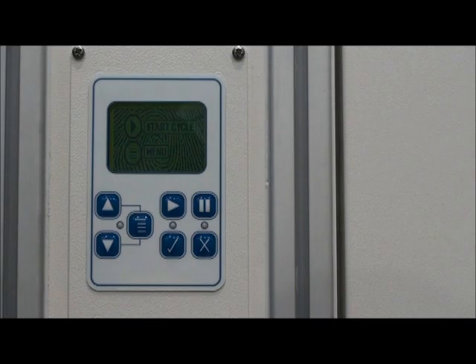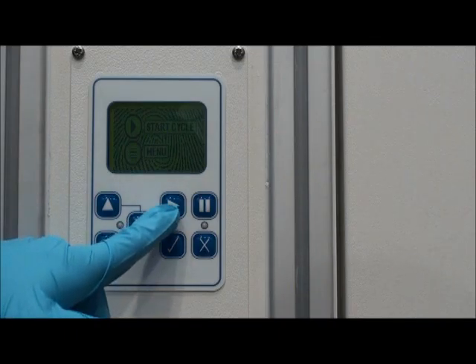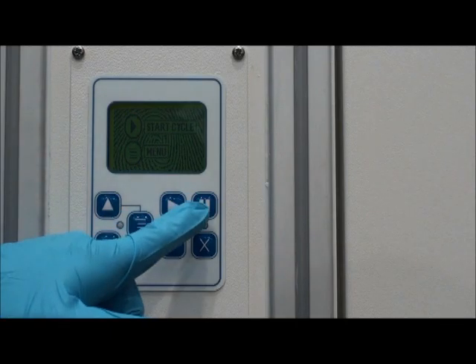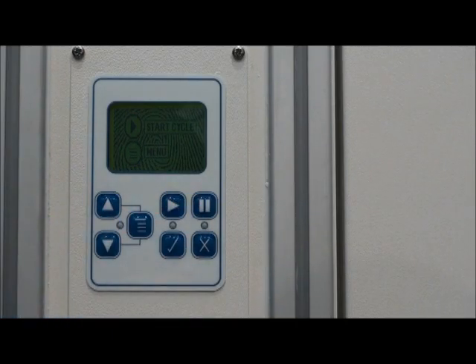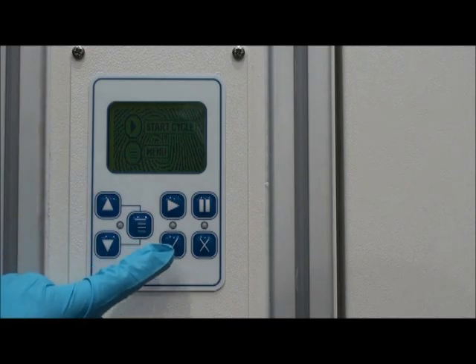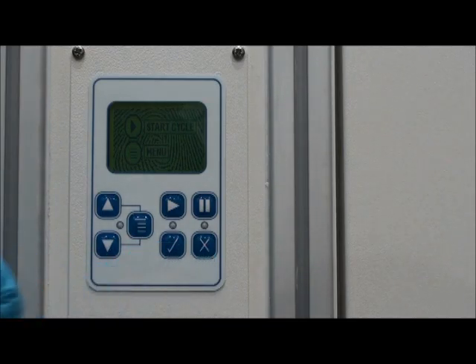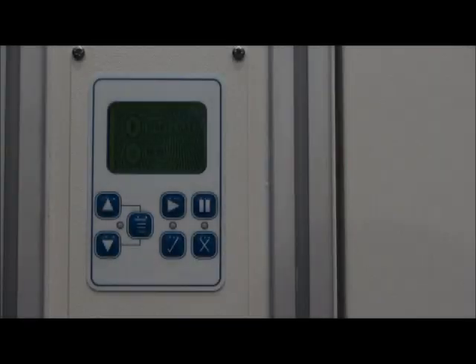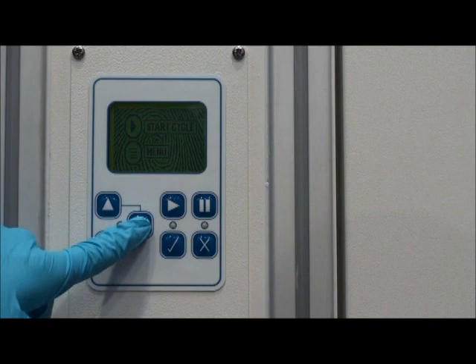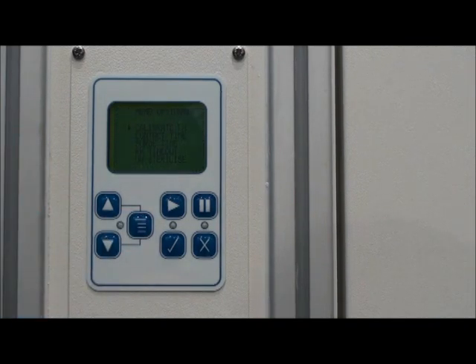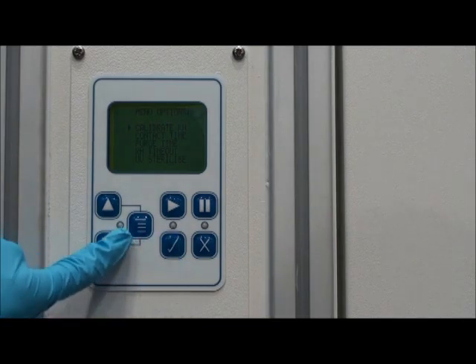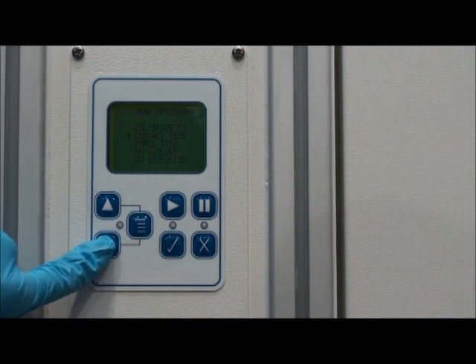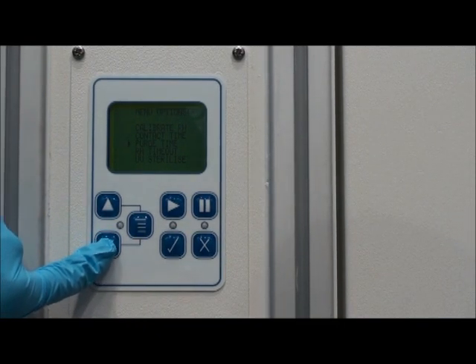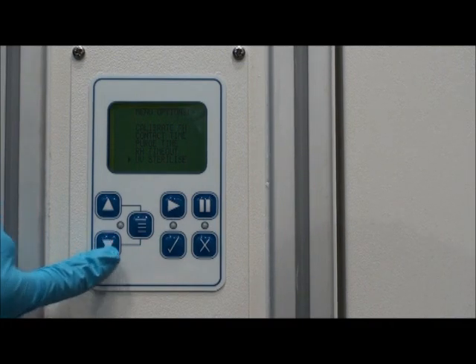The next key is the arrow key, which is the start cycle key. Next to it is the pause key, which is used to pause or abort the cycle, and below that are a tick and a cross. Those keys are used to accept and reject commands once in the submenus. Now we're going to examine the menu. Once you press the menu key, you'll see the submenu, which lists calibration, contact time, purge time, RH timeout, and UV sterilize.